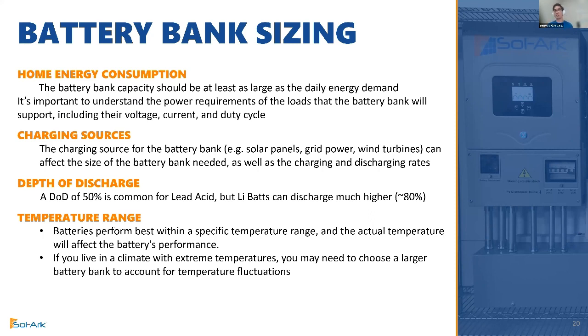So we do always recommend to our customers that are not worried about EMPs lithium batteries, which can discharge much higher, towards around 80% of depth of discharge. Another factor that affects the battery bank sizing is the temperature range at which the batteries will perform. They perform best at a specific temperature range, and the actual temperature does affect the battery's performance. For example, if you charge your battery while it's below freezing, that could definitely have some negative consequences to the battery.